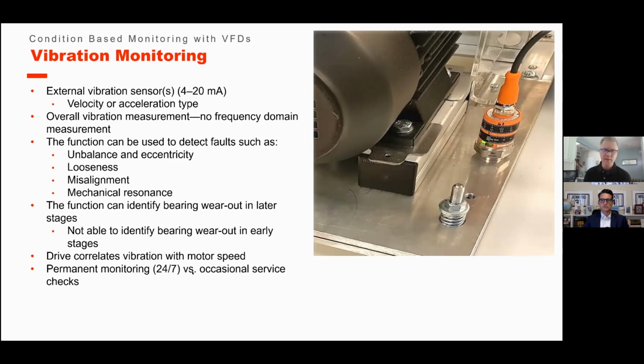Like I said a couple seconds ago, if you have a PM program where you're running around once a quarter and doing vibration measurements with a tool, that's at that moment in time. So 10 minutes from that time, you don't know what's happening. With this software, you know what's happening 24/7. As that machine is running, from when it starts to when it ends, you're monitoring it. That's like having somebody with a tool just sitting there monitoring your equipment. So it's very unique. Lastly, let's talk about the load envelope.